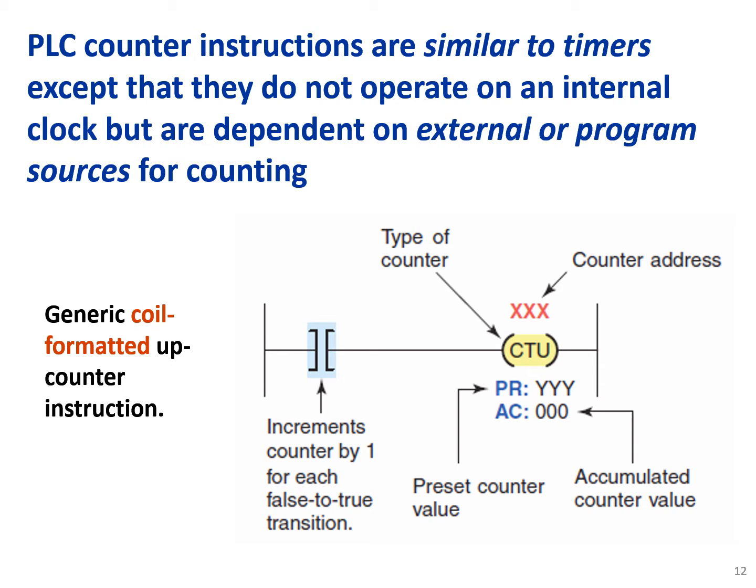PLC counter instructions are similar to timers, except that they do not operate on internal clock, but are dependent on external or program sources for counting. So timers are used based on the internal clock, but not the counters. Counters get the signal from the sources outside of the PLC.